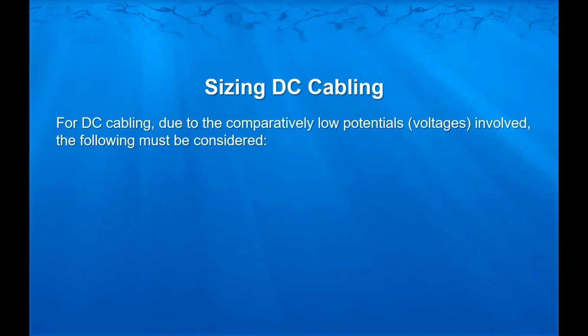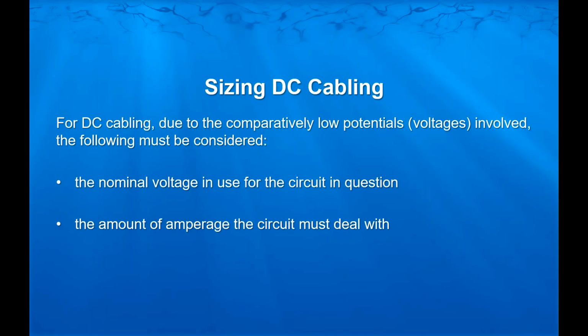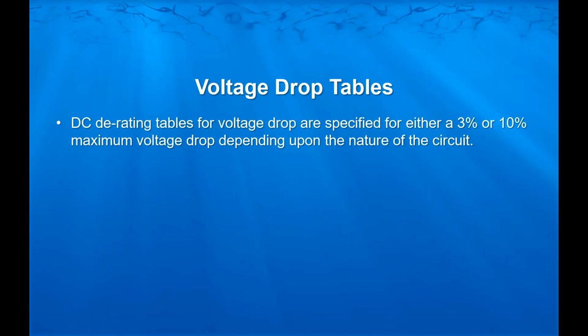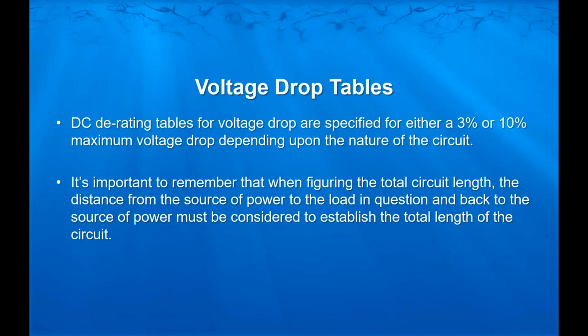So for DC cabling, due to the fact that we have a comparatively low potential, our voltages are much lower. We're 12, 24 most of the time. We've got to consider the following: what that nominal voltage is for the circuit in question, the amount of amperage that we're asking the circuit to deal with, and the total length of the circuit. So we have voltage drop tables to deal with this issue. And these voltage drop tables are specified for either 3% voltage drop or 10% maximum voltage drop, and that depends upon the nature of the circuit.